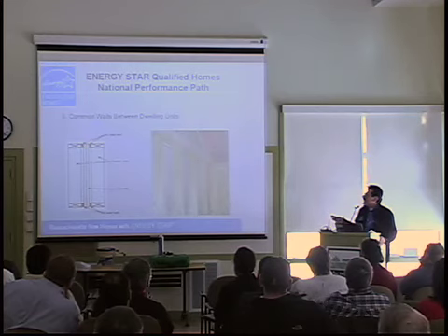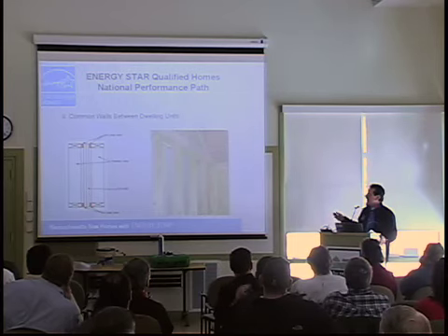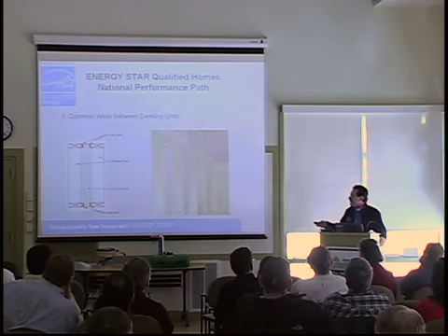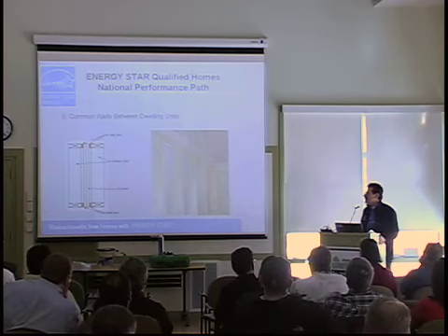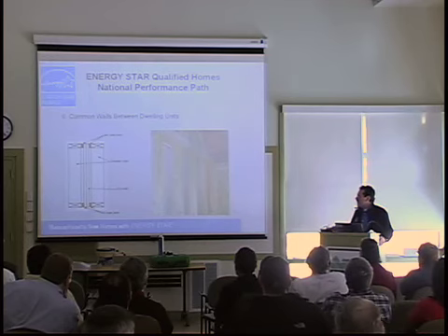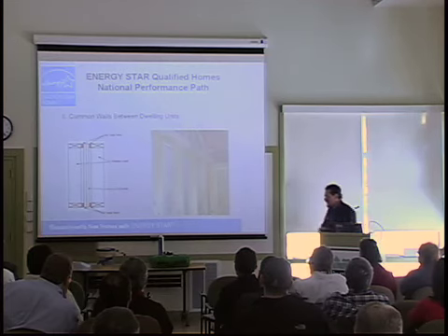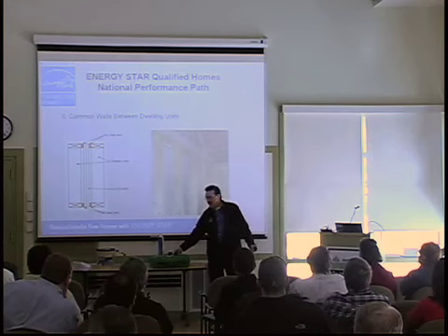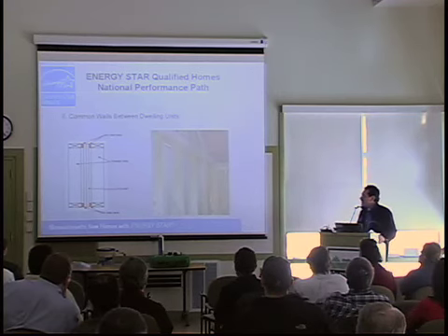The other area, how many of you do attached family housing? More than one unit, more than single family homes? All right, then you need a firewall between them. I've seen enough firewalls go in as poorly as they go in well, but you really need to seal up all the penetrations. You don't want air moving. So between all the floors, top and the bottom, you need to seal that up. It being a firewall, you can't use a regular foam gun. It stops the flow of air. You need some sort of intumescent caulking, fire-rated caulking, and that'll pass the thermal bypass inspection as well.